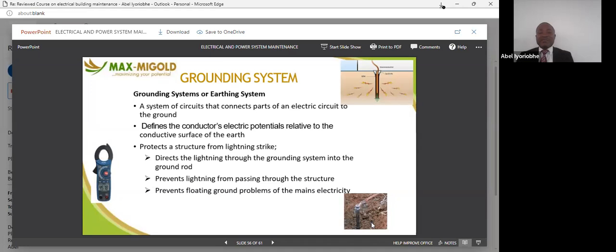The resistance of the earth is very low. That's why fault current tends to flow to the weaker point. The earth is a weaker point compared to your installation, to your equipment. So the earth conducts fault current from your installation or from your home to the ground. Current that is capable of putting your house on fire, current that is capable of killing a soul in the house or in the facility, will be conducted to the earth.